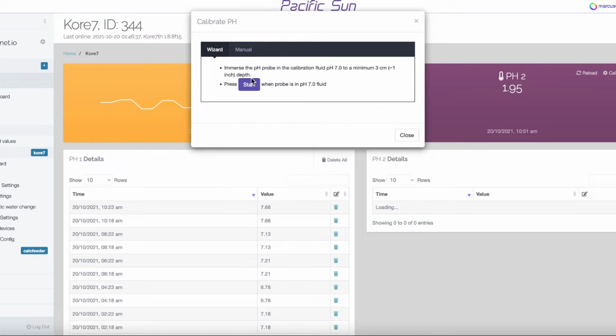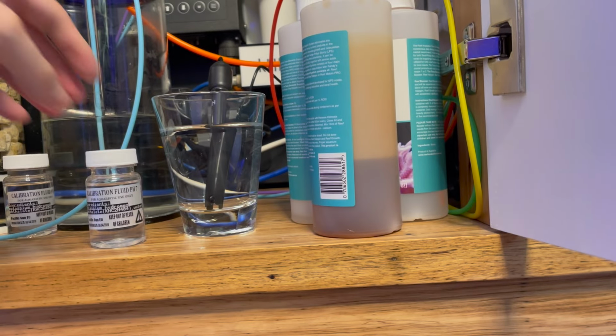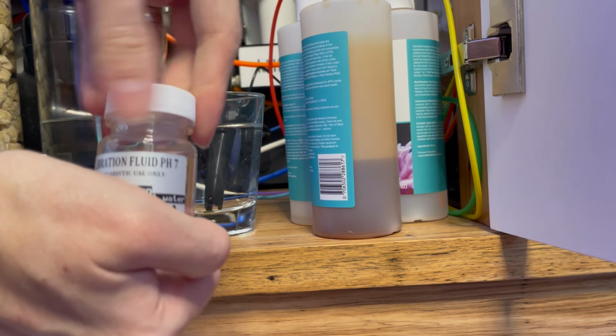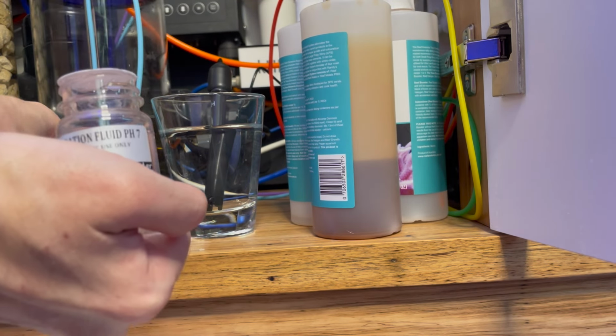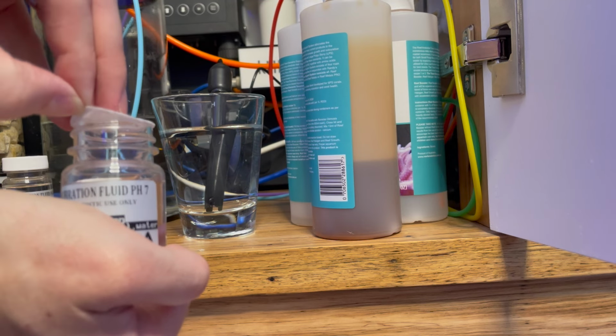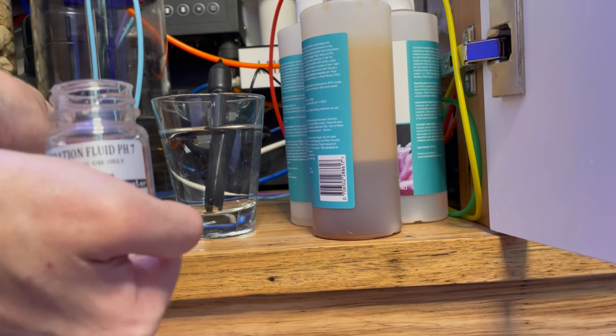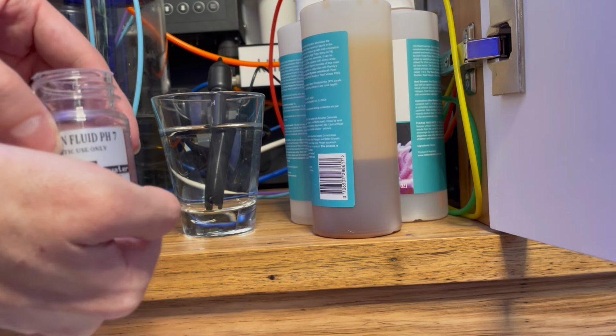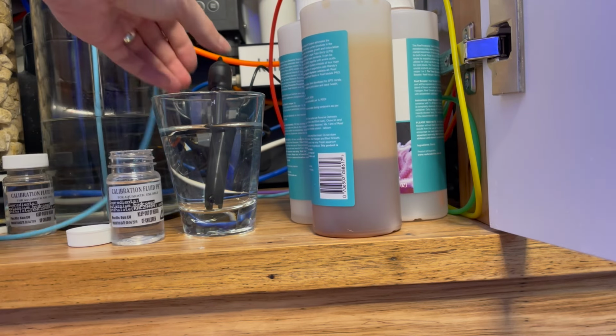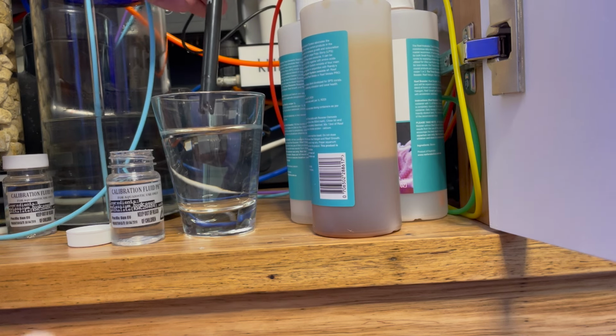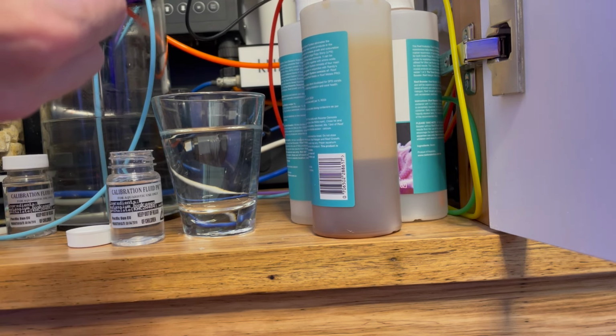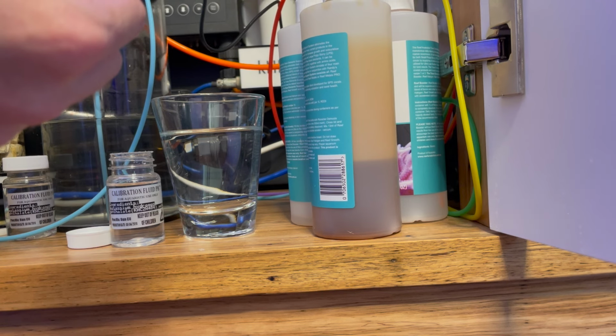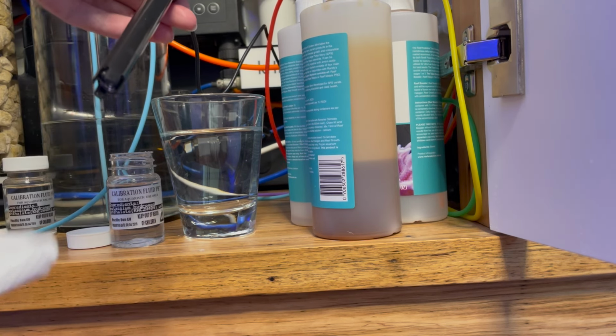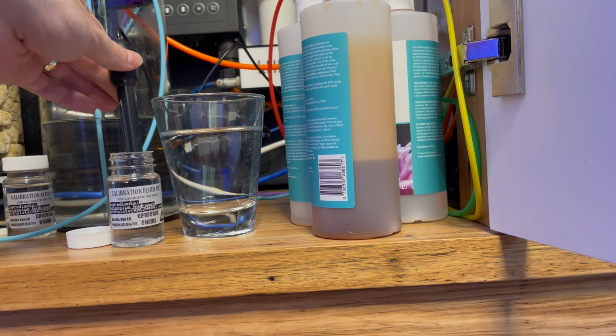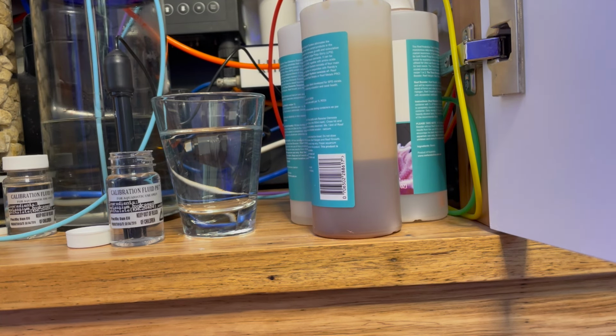All right, as you can see, we're going to put the probe into the pH 7 and start the timer again. Taking pH 7, remove the seal, just dry the RO water off the probe and very gently dab any excess and place it into the pH 7 calibration fluid.